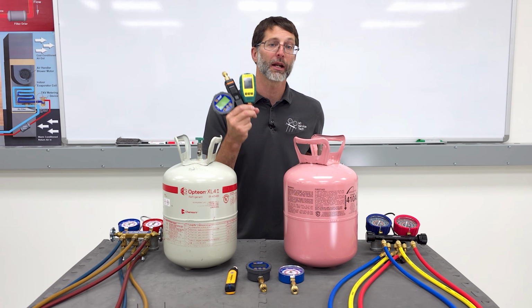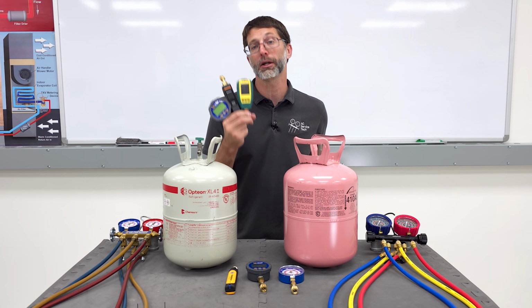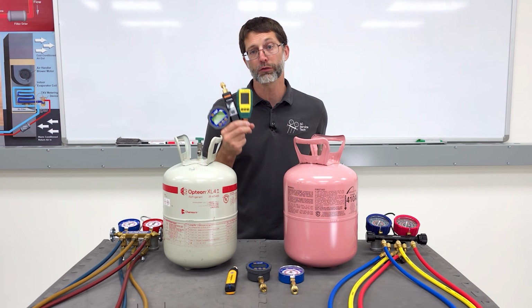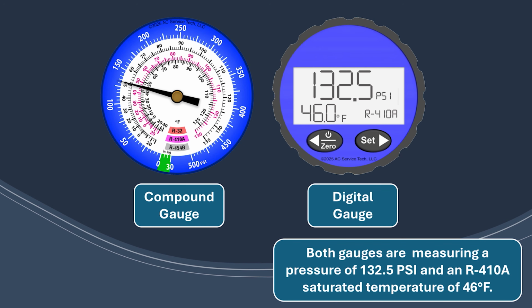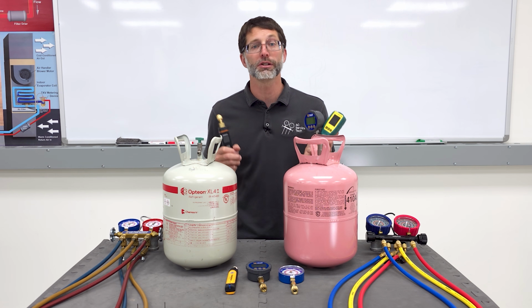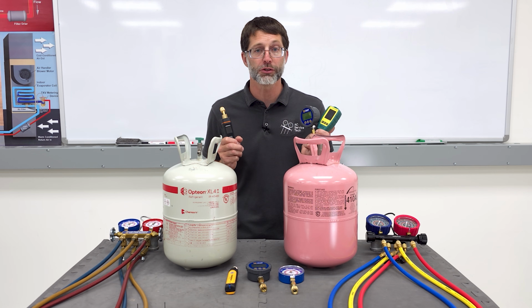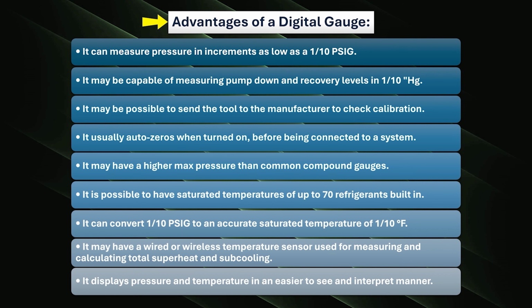For the sake of automatic pressure to temperature conversions and accuracy, use digital gauges whenever possible. See Figure 432 to compare the display of a compound gauge to a digital gauge. Both gauges are measuring a pressure of 132.5 psi and displaying an R410A saturated temperature of 46 degrees Fahrenheit. The advantages of a digital gauge and disadvantages of a compound gauge are listed as follows. Advantages of a digital gauge. It can measure pressure in increments as low as 1/10 of a psig.